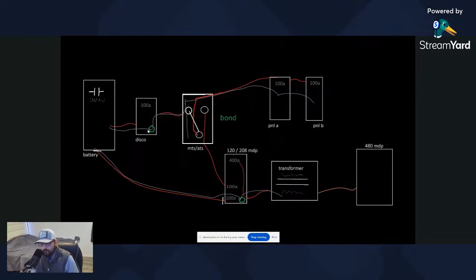If we have a ground fault, if we've got current or a short circuit or something on something metal, we need to get that current off of whatever's metal, bring it to our ground bar, and our neutrals are bonded to our ground bar, and that's going to get current back to the source. And that's effectively the only way to trip the breaker on a ground fault, is if you've got that connection where your grounds and neutrals are bonded.